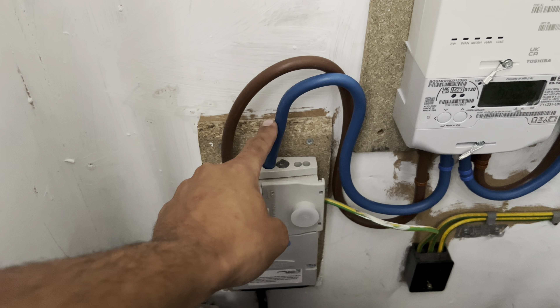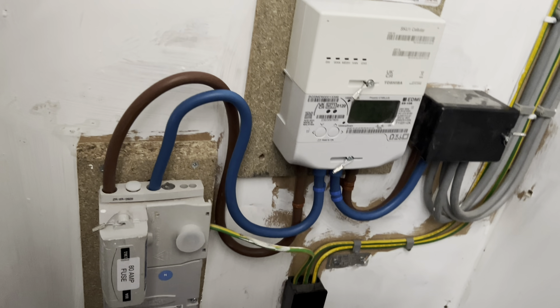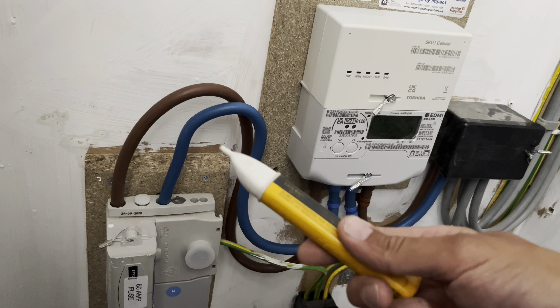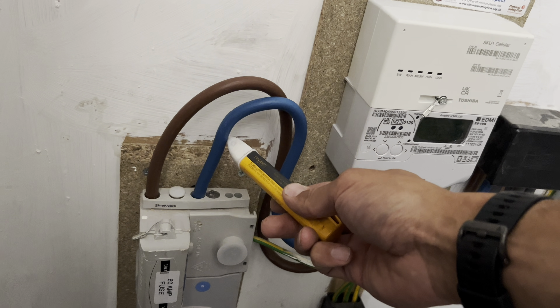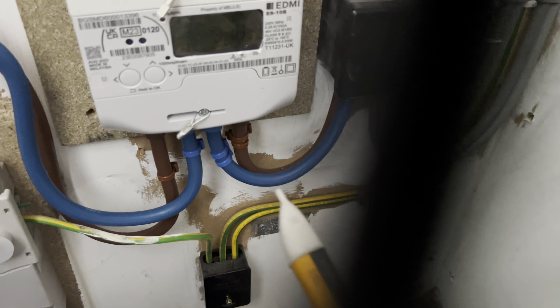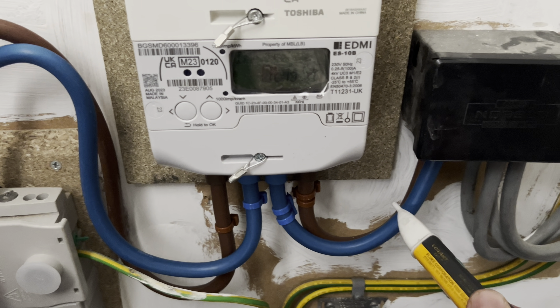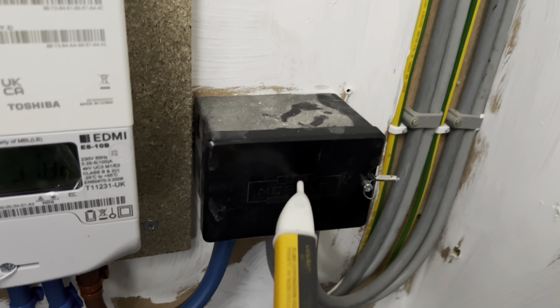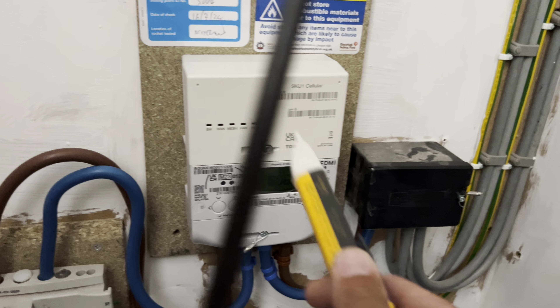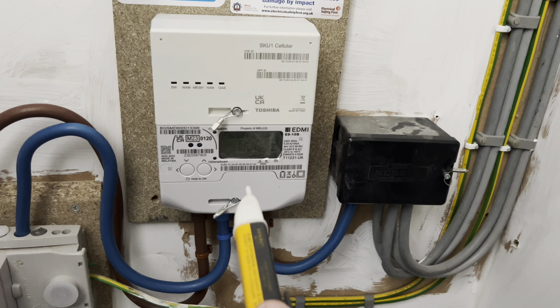You've got your fuse here, so the live will be on this side and neutral on this side — that's correct coming out of it. We can't get to these terminals because they're owned by the DNO — we're not legally allowed to touch the connections. However, I can put my trusty pen on here. The neutral — this flashes just to let you know it's on, that doesn't mean it's live. This is live exactly as it should be coming out this side. On these meters, the lives are always on the outside and neutrals on the inside. Still correct — neutral here, live here. And where the problem has begun: the polarity is correct around this way, but what they've done is they've replaced this meter, and by replacing it the live and neutral are the correct way going in — but what they've done coming out is wrong.